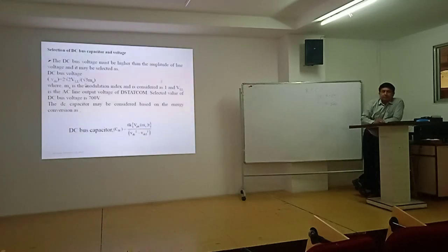How much will it come? 2 root 2 into 415 divided by root 3. How much? 2 root 2 into 415 divided by root 3, around 600-something. So that is the minimum requirement by calculation. Okay. So a round figure value can be taken. Round figure we have taken 700.